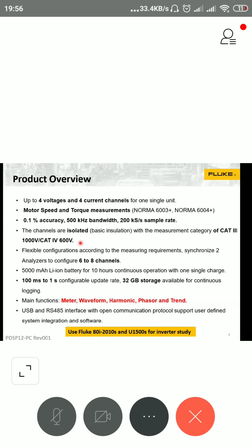Now, I was talking about the transient, right? If there is a sudden transient or a sudden spike occurring from the utility, and you have connected a device to the electrical panel, that transient may be several kilovolts. When you are working in an electrical panel, as per safety guidelines, it falls under category 4. When you're using category 4 equipment and measuring 230 volts or phase-to-phase 450 volts, if there is a surge, it may be up to 8 kilovolts.